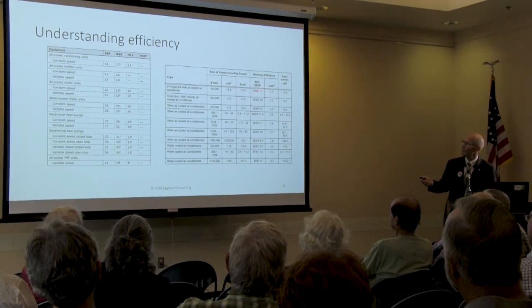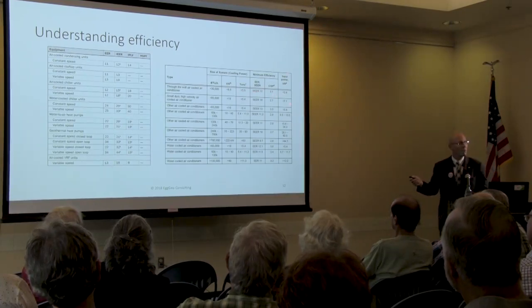It says it has a COP of 3.1 input power. Now think about what we just learned. The input power is 2.8 kilowatts. For 2.8 kilowatts, I get 8.8 kilowatts of delivered energy movement. And that's what that means. If you divide 8.8 by 2.8, you get 3.1. That's how it happens.